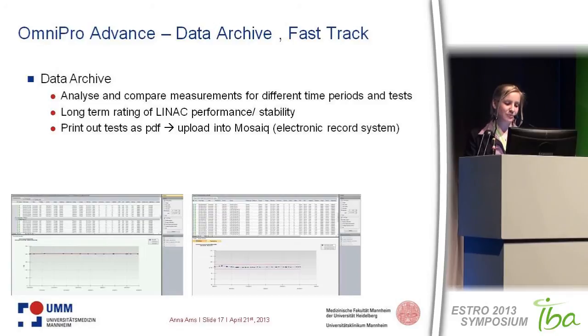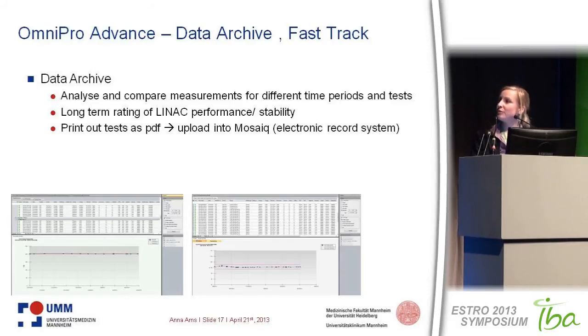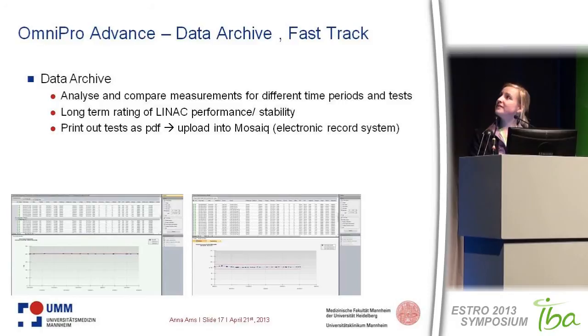The third section of OmniPro Advanced Software is the data archive, and it is a very useful and efficient tool. You can analyze and compare measurements across different time periods, see what happened if a Linac is no longer performing well, and have a long-term rating of stability with a trend analysis. You can print out tests and store them in your database — for example, we upload them into Mosaiq for safety.